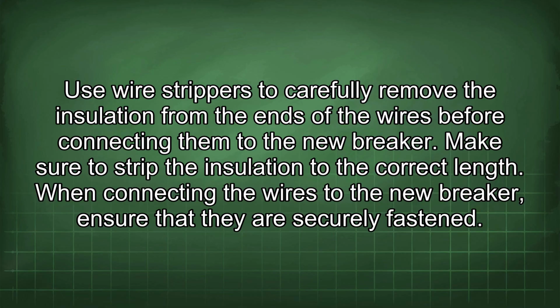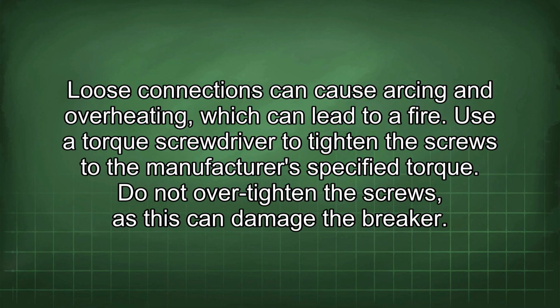When connecting the wires to the new breaker, ensure that they are securely fastened. Loose connections can cause arcing and overheating, which can lead to a fire. Use a torque screwdriver to tighten the screws to the manufacturer's specified torque. Do not over-tighten the screws, as this can damage the breaker.